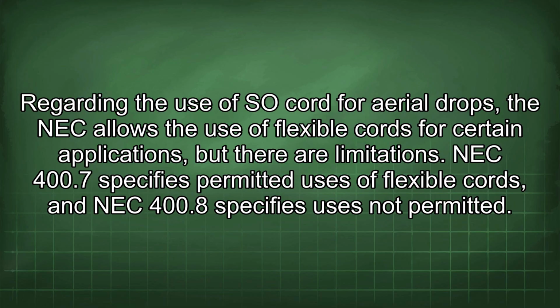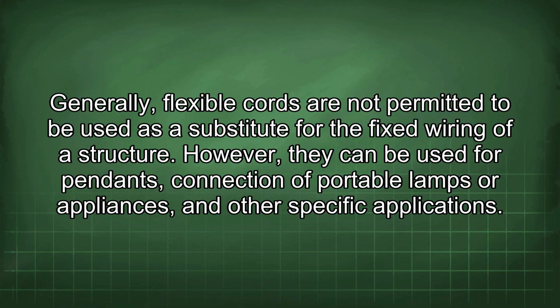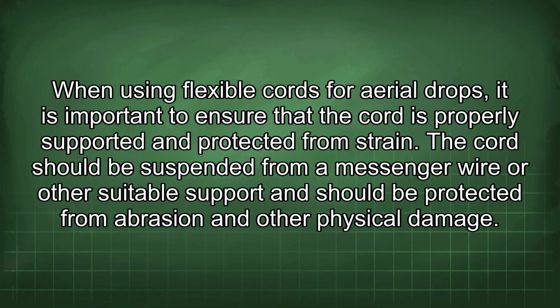Regarding the use of SO cord for aerial drops, the NEC allows the use of flexible cords for certain applications, but there are limitations. NEC 400.7 specifies permitted uses of flexible cords, and NEC 400.8 specifies uses not permitted. Generally, flexible cords are not permitted to be used as a substitute for the fixed wiring of a structure. However, they can be used for pendants, connection of portable lamps or appliances, and other specific applications. When using flexible cords for aerial drops, it is important to ensure that the cord is properly supported and protected from strain. The cord should be suspended from a messenger wire or other suitable support and should be protected from abrasion and other physical damage.